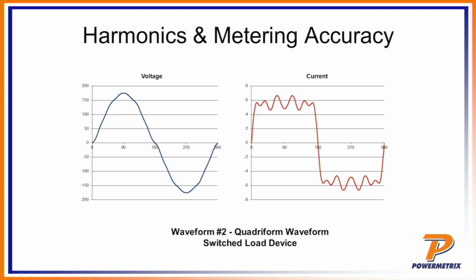The second waveform we're looking at is the quadriform waveform. Here we have the waveform defined in both voltage and current. Voltage is still fairly sinusoidal, with a little bit of lumps and bumps, but the current waveform is a very square waveform. Once again, a square waveform, as we saw early on in this presentation, is made up of many odd harmonics. This is a switched load device, so you may have a system switching positive and negative, thereby generating this square-wave-looking current waveform. It has a lot of harmonic energy and could potentially cause some problems for meters, because they don't like those extra harmonics at the higher orders.